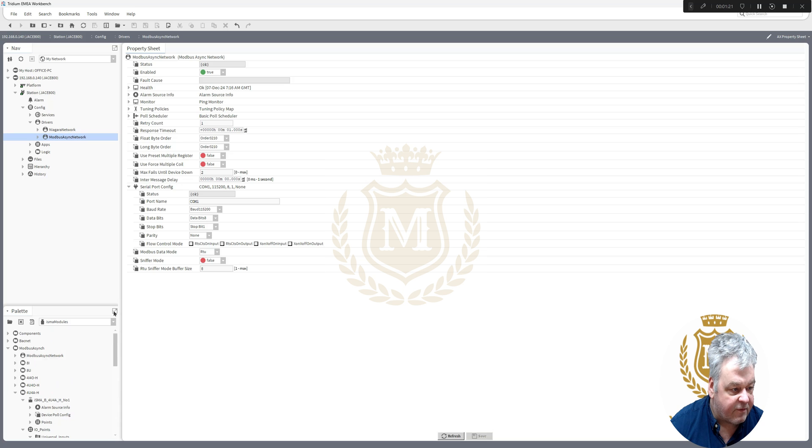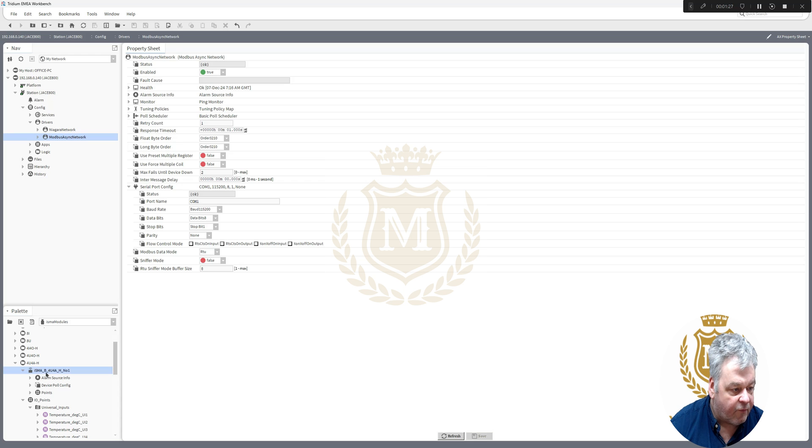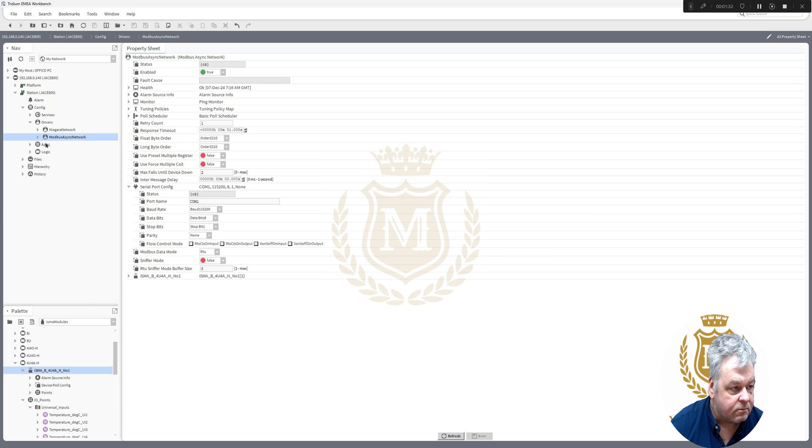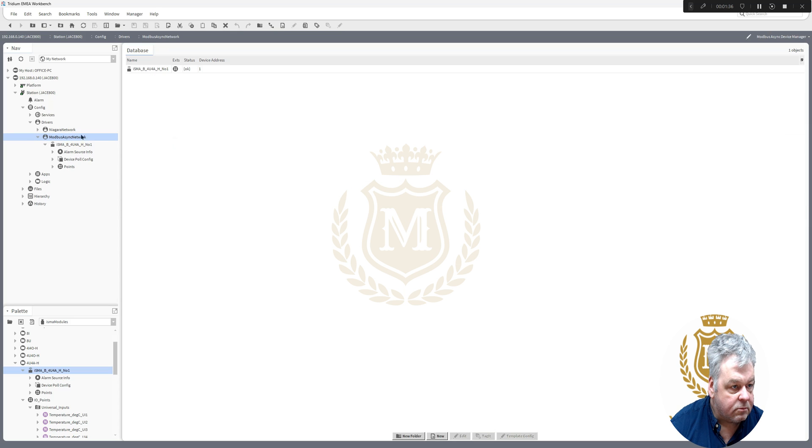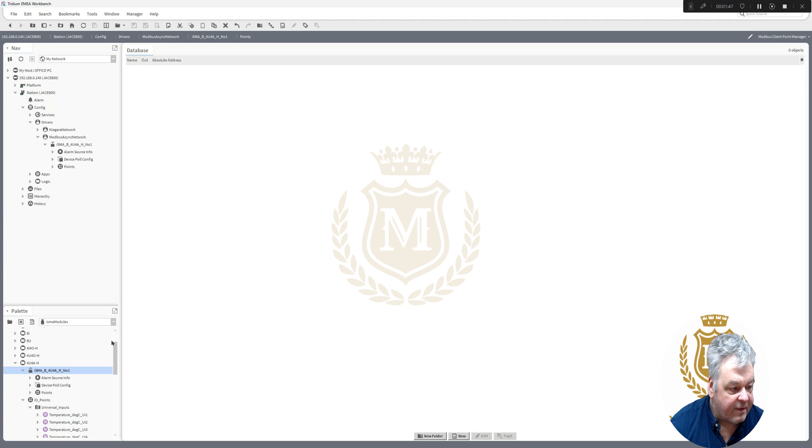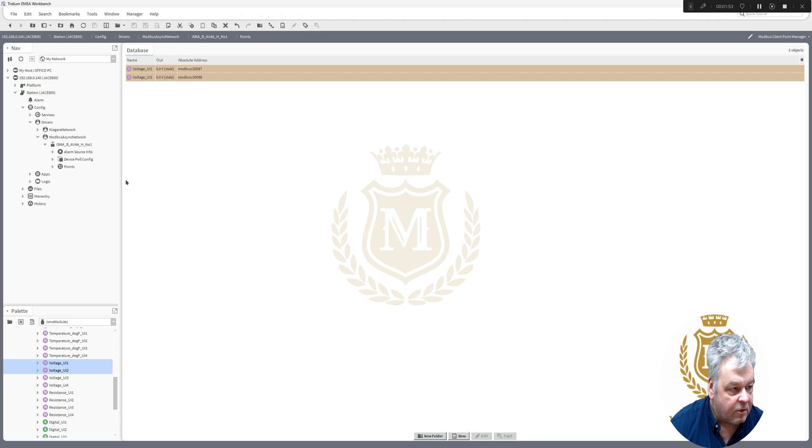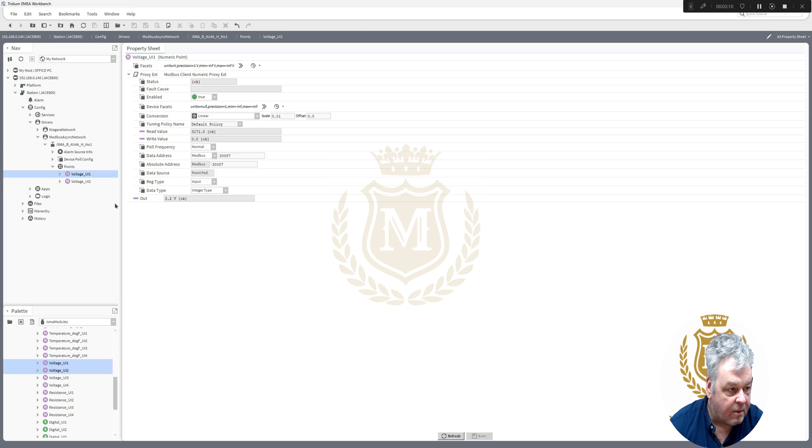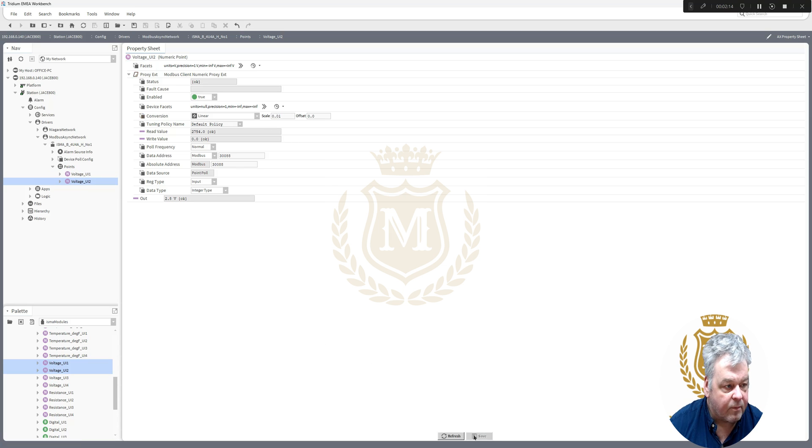And then in the ISMA modules in the palette, we select 4U4A. That's what I've got connected there. That's showing that connected on device 1. These are the points that come in there. We're not interested in any of those points, so I can delete them out. And I want voltage U1 and U2. U1 being my humidity. These are not showing the right settings at the moment, so let's just move that scale down one. And we'll move that scale down one. That's our temperature.